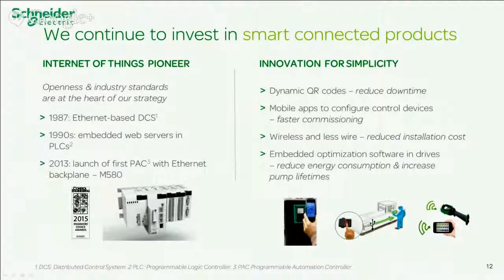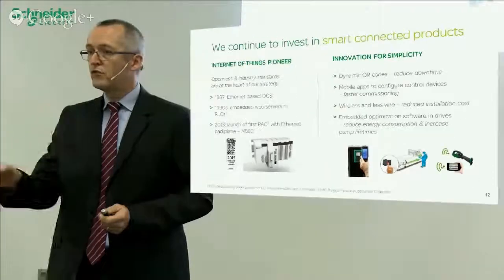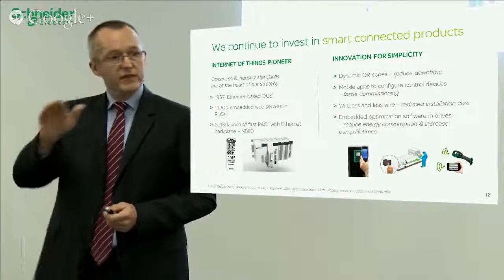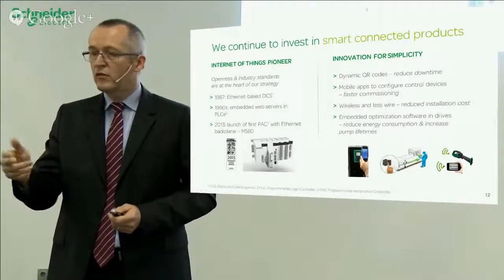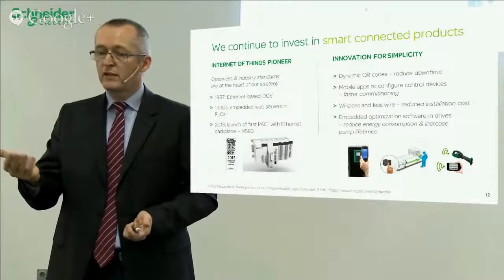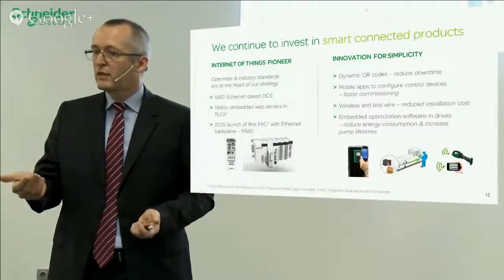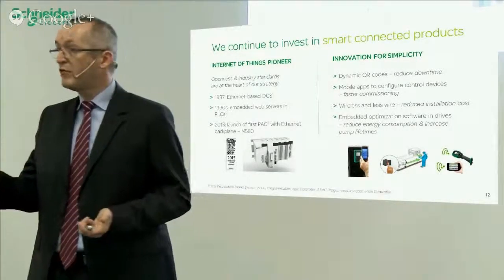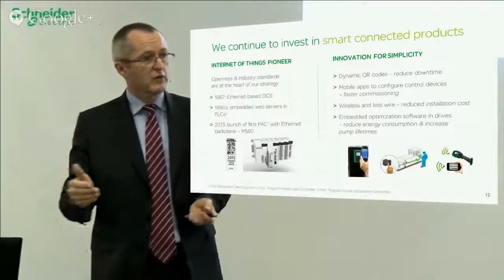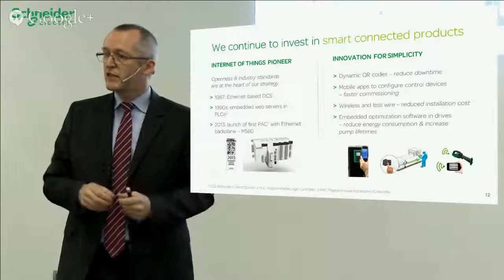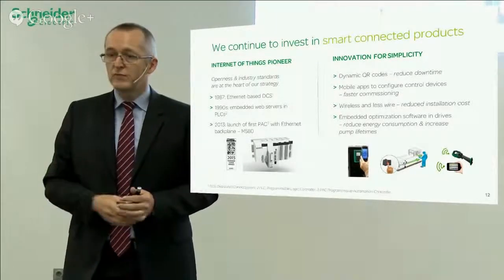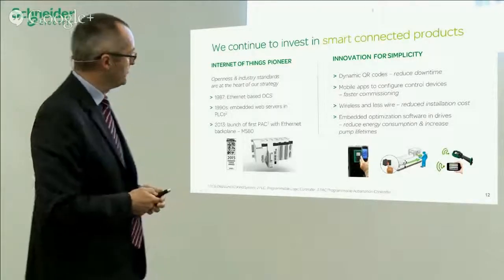And finally, embedded intelligence. Again, the example here is our drives - we are embedding intelligence inside the drive. For example, we can embed the pump curve inside the drive, which means we can monitor where the drive is running on the pump curve. If we detect that the drive is running most of the time on the wrong part of the pump curve, we can correct that. That's very important, because if you run a pump in the wrong part of the pump curve, you wear the pump out very quickly and consume a lot of energy - it's not very efficient. So these are simple things, embedding intelligence inside the products in the field to bring tangible benefit to an end user.